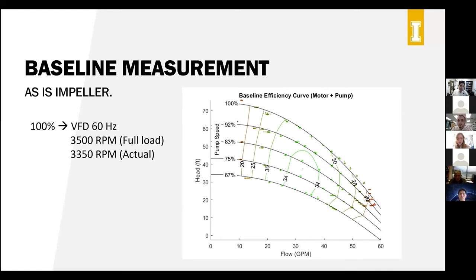This efficiency is a combination of both motor and pump, measured by the power meter. On the x-axis, we have flow, varying from mostly 10 to 60 gallons per minute, and head ranging from 10 feet to about 75 feet. One thing you might notice is that the most efficient portion of this pump, unlike in a typical pump curve, is not at 100% of the speed. 100% of the speed means the VFD was set at 60 hertz, and then 92% would be the VFD set at 55 hertz, then 50 hertz, 45 hertz, and 40 hertz. So a couple of noticeable things: the maximum efficiency occurred at around 83 to 75% of VFD speed. In most pump curves, as I said, the most efficient point would be at 100% speed.